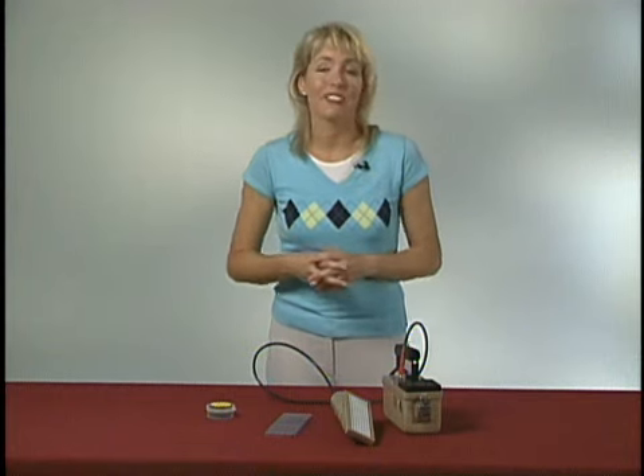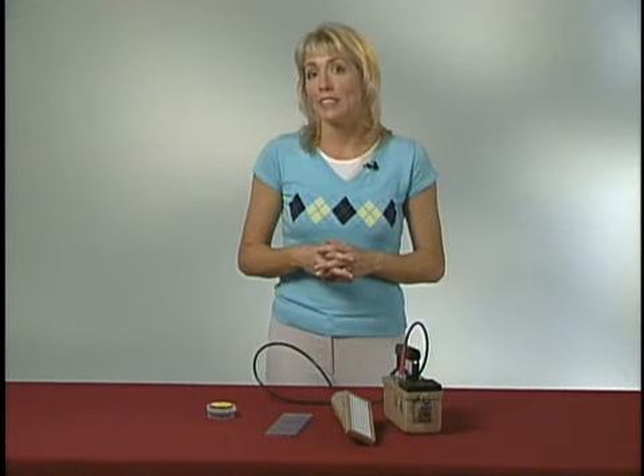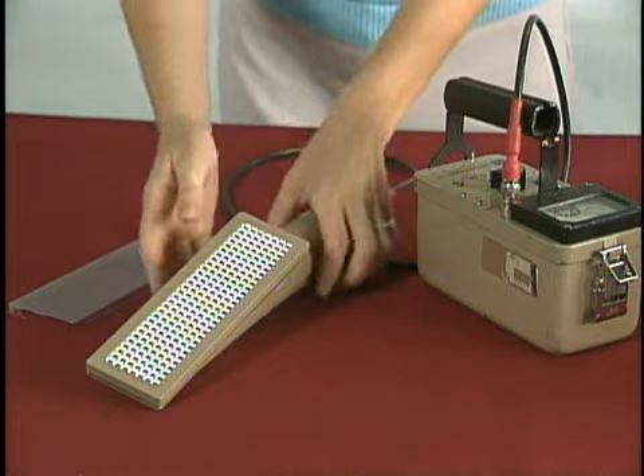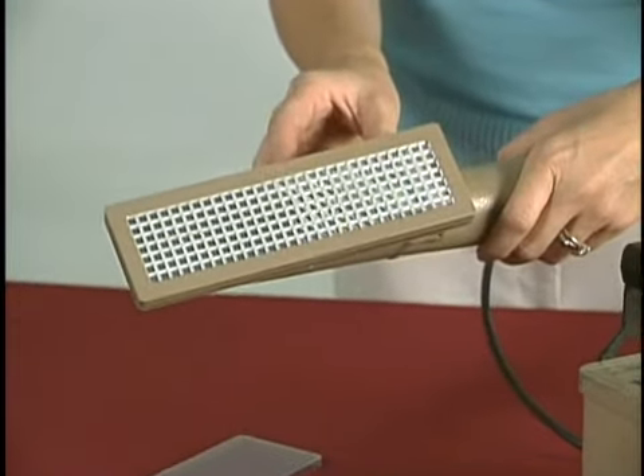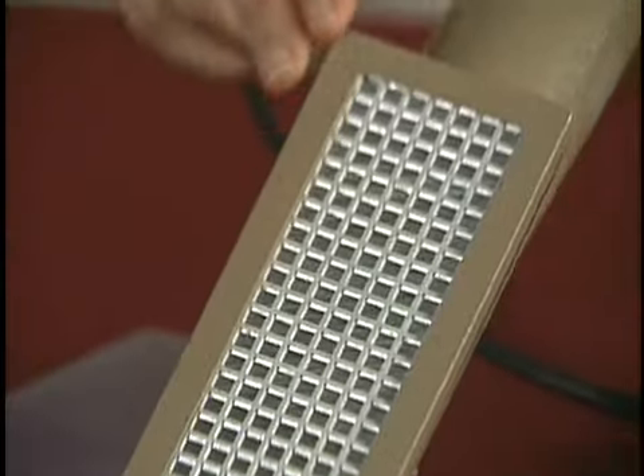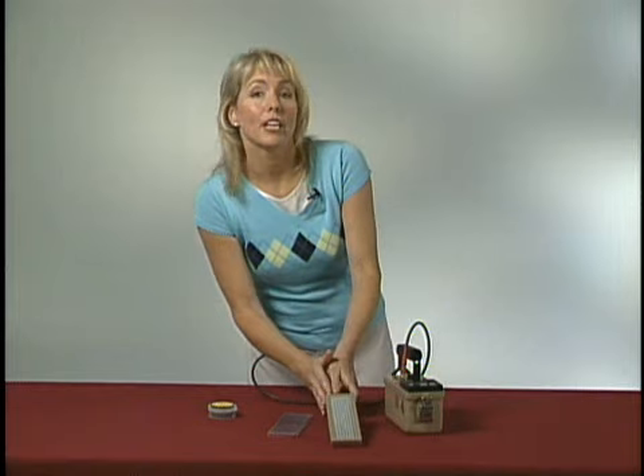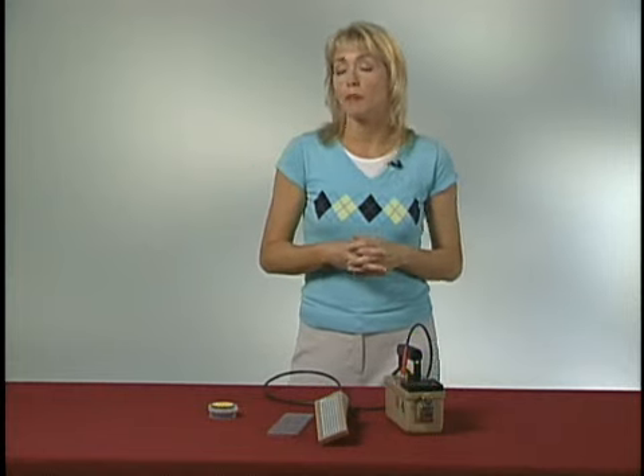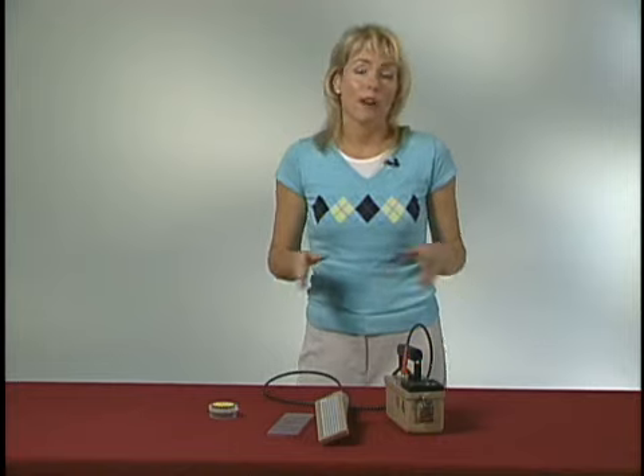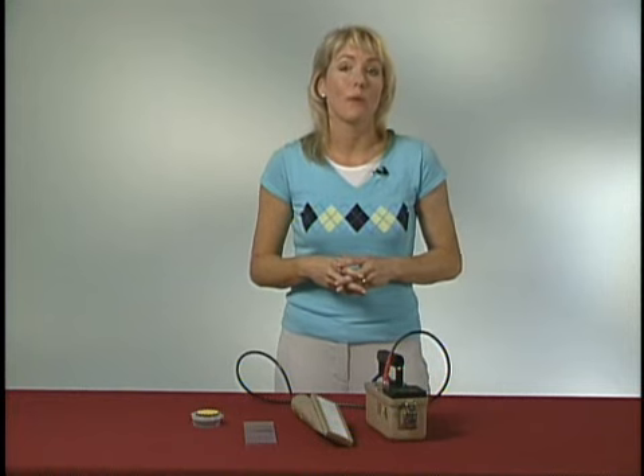Now for some specifics about alpha scintillators. For an alpha particle to reach the zinc sulfide scintillator and cause a flash of light, it must penetrate a very thin window of aluminized mylar. The light is then reflected to the photomultiplier tube, which is located in the handle of the probe. A major advantage of the zinc sulfide alpha scintillator is the fact that it only responds to alpha activity. It does not detect beta particles or gamma rays. And since there is relatively little alpha activity in the background, the alpha scintillator should read 0, 1, or maybe 2 counts per minute in an uncontaminated environment. If you have a higher count rate than that, you need to determine what is happening. Because of its low background count rate, the zinc sulfide scintillator is the instrument of choice for locating alpha contamination on people or other surfaces.